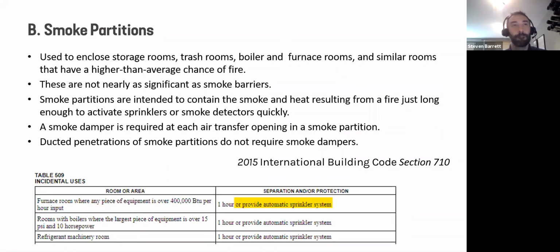Now, a smoke partition is a little bit less stringent than a smoke barrier, and these are used to enclose rooms that are higher than normal hazard, like a storage room, a trash room, boiler and furnace. And if you're familiar with building codes, you might have seen this table below. If not, it's table 509 from the IBC, and it requires all these different types of rooms because they're an incidental hazard. If you meet these criteria, you have to provide whatever's on the right. So for example, furnace room, any piece of equipment over 400,000 BTU per hour input, it says provide 1-hour separation or provide an automatic sprinkler system.